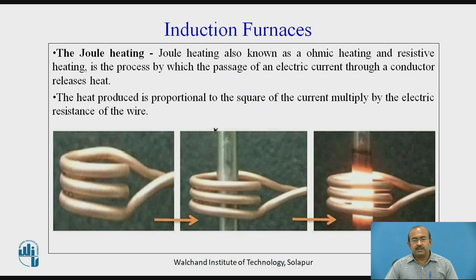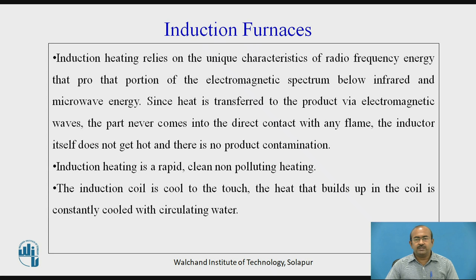A three-stage image shown on screen illustrates how the raw material or base metal changes color due to heat evolution. Induction heating relies on radio frequency energy from the portion of the electromagnetic spectrum below infrared and microwave energy. Since heat is transferred via electromagnetic waves, the part never comes into direct contact with any flame. The inductor itself does not get hot, resulting in no product contamination. Induction heating is rapid, clean, and non-polluting, and the induction coil is kept cool by constantly circulating water.